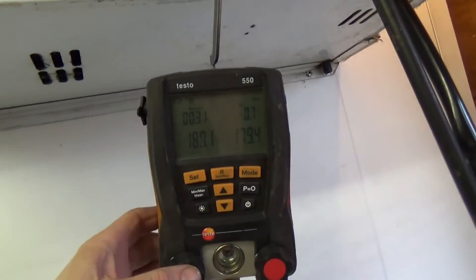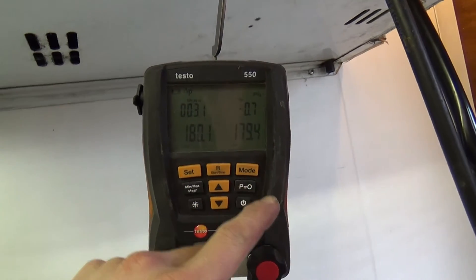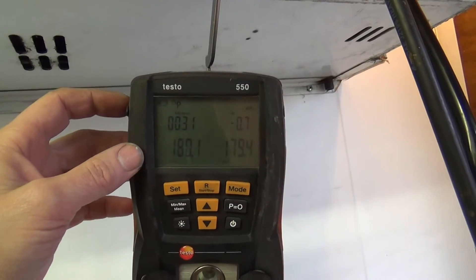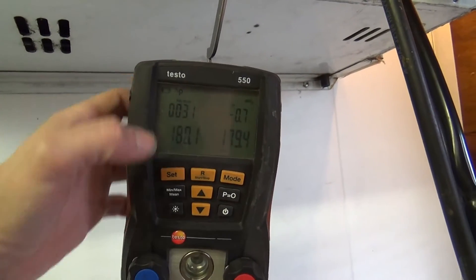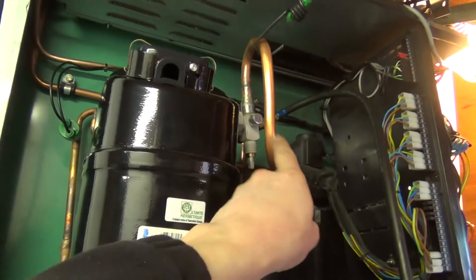It's been on test for half an hour. It dropped 0.7 while I had lunch and it's not dropped in the 10 minutes since. So I think I probably started the timer before we equalized because we were only connected on the load side. We've got to sort out the electrics.